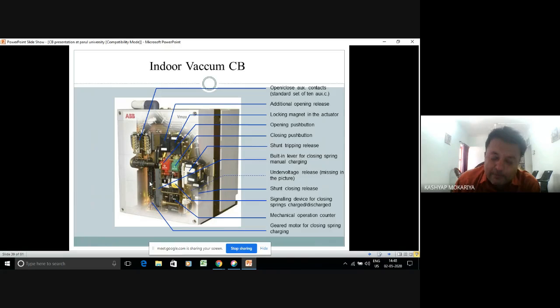The selected breaker has passed the type test, the routine test. And then the inquiry will come: at that production lot, who was there, what production care was taken at the time in industry, and all those things will be noted. Now the routine test is done for all individual breakers. The routine tests are performed for the healthiness of the breaker. Commissioning test.